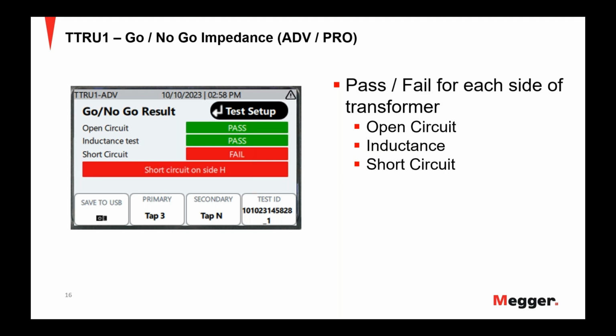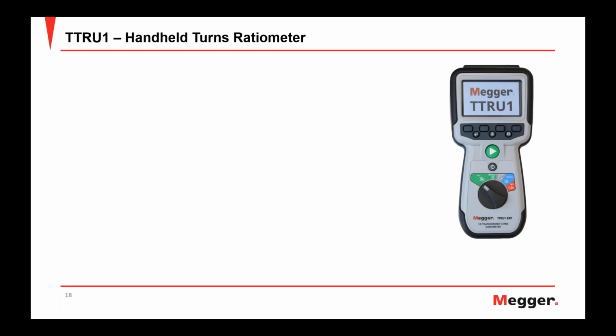So in summary, the TTRU1, the latest truly handheld turns ratiometer from Megger, is a single phase source and measurement instrument for single phase and three-phase distribution, power, and instrument transformers that measures, of course, turns ratio, that go no go test, or the pass fail test that we talk about.